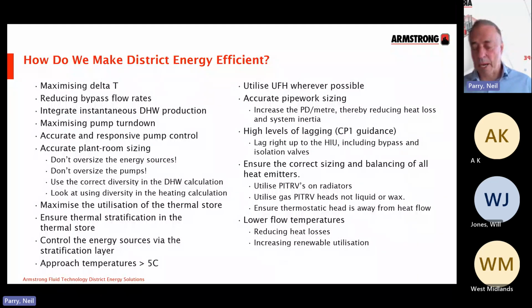We need to also look at bypasses, and it's a key area. CP1 itself says we need to reduce the number of bypasses on the system. We have to remember, of course, that a keep warm or a standby flow rate through a HIU or terminal unit is a bypass. So we need to think about that. We need to be very careful about selection of equipment to make sure that we reduce that bypass flow rate wherever possible. Select equipment that manages that bypass very well. But also, if we calculate that we need to have some system bypasses somewhere on that system, that's okay, but we need to make sure that we valve it correctly and commission that valve correctly, so that flow rate through that bypass is kept to an absolute minimum.